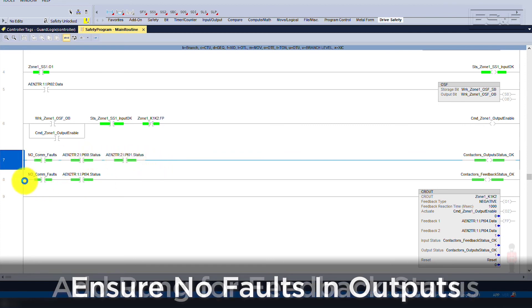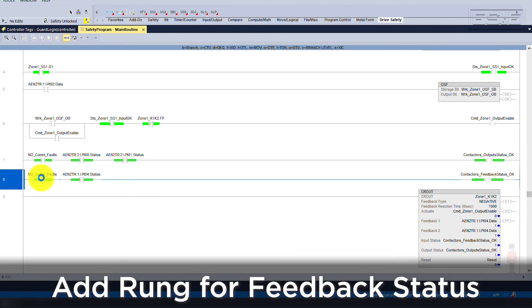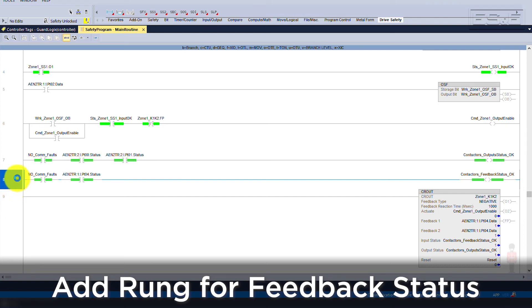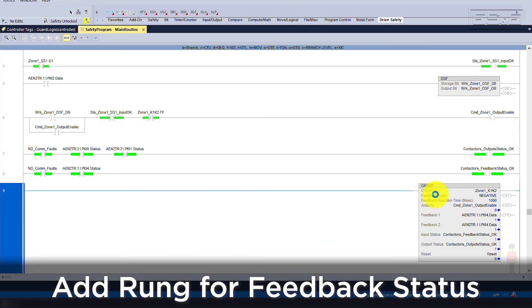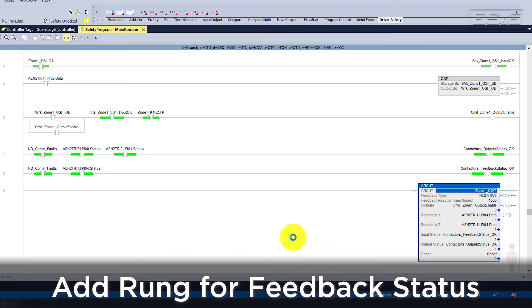With outputs, we also need to monitor the feedback signal, so another rung can be created for feedback status. But if you are using a standard I/O point, then you can implement that logic outside of the safety routine. Feedback and output statuses are both needed for the Configurable Redundant Output instruction.